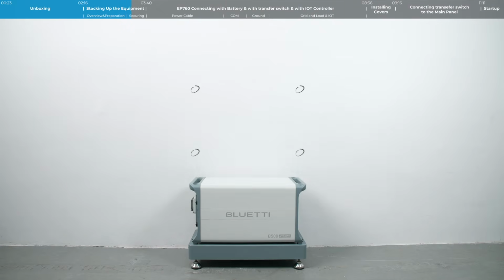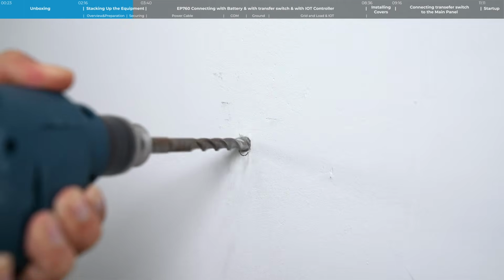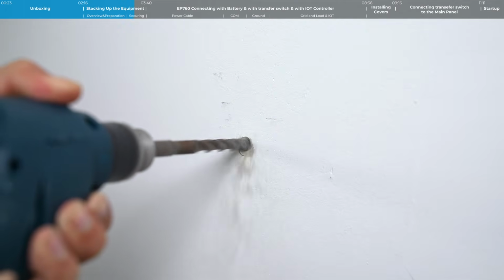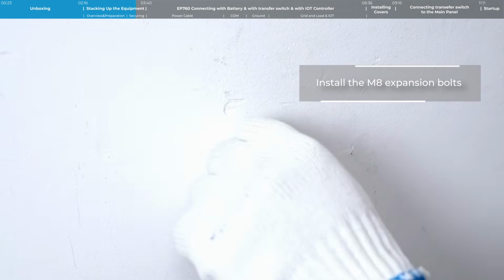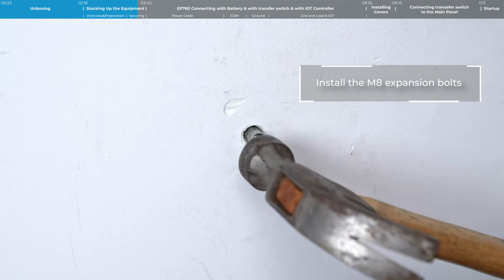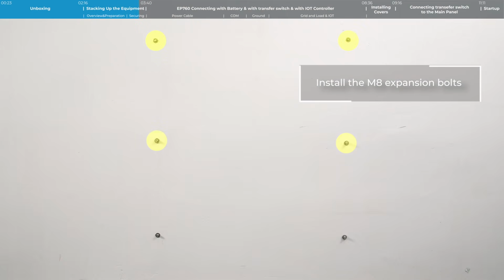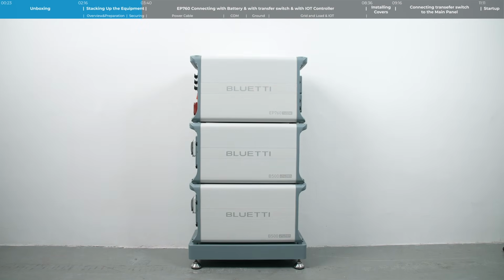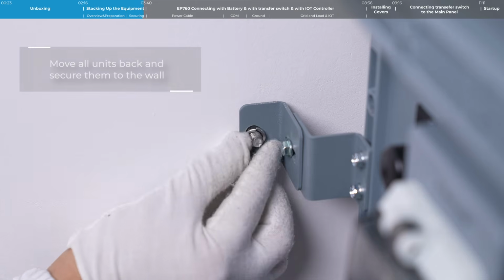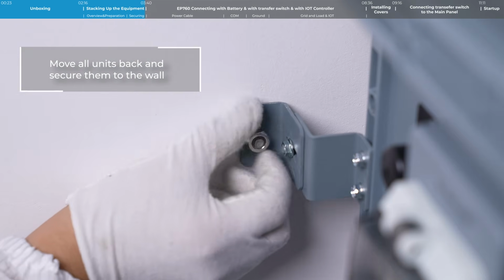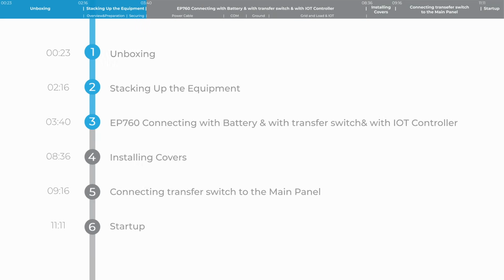Remove all units. Drill a pilot hole at the marked position. Hammer in the expansion bolt until it's flush with the wall. Repeat the same process for the remaining pre-drilled holes. Finally, move all units back and secure them to the wall. Step 3. Connecting the battery with the sub-panel and the IoT controller.